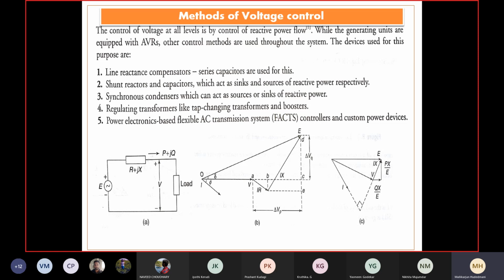Basically, voltage control is done through the AVR, the automatic voltage regulator control loop situated around the generator. But due to the various factors on which voltage is dependent, it needs to be controlled from different ends itself. Therefore, the delivery of power from the generating station to the receiving station over the transmission line again adds reactance to the system, inductiveness to the system, an additional drop in the system, which definitely causes the system to become more sluggish and inferior in that perspective. Therefore, the voltage profile definitely gets affected.